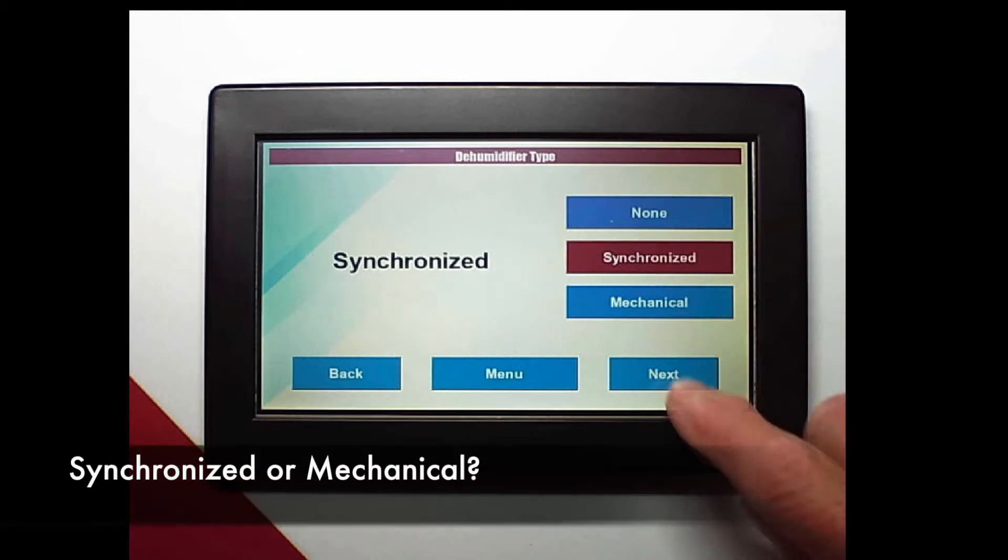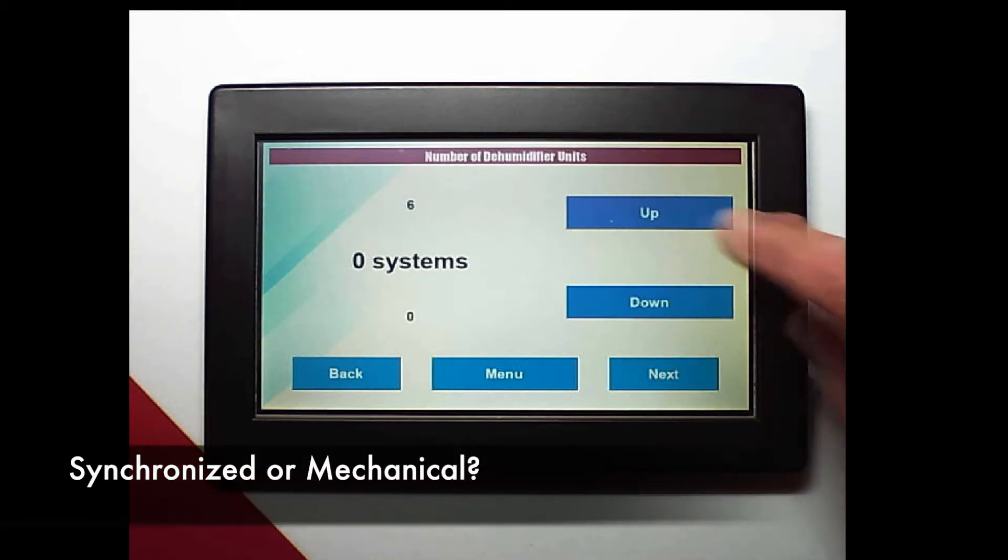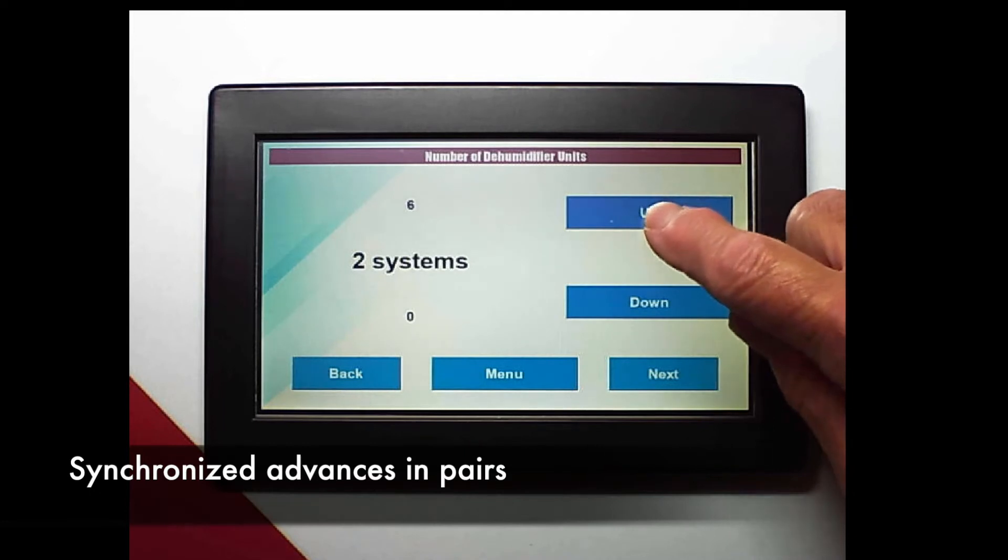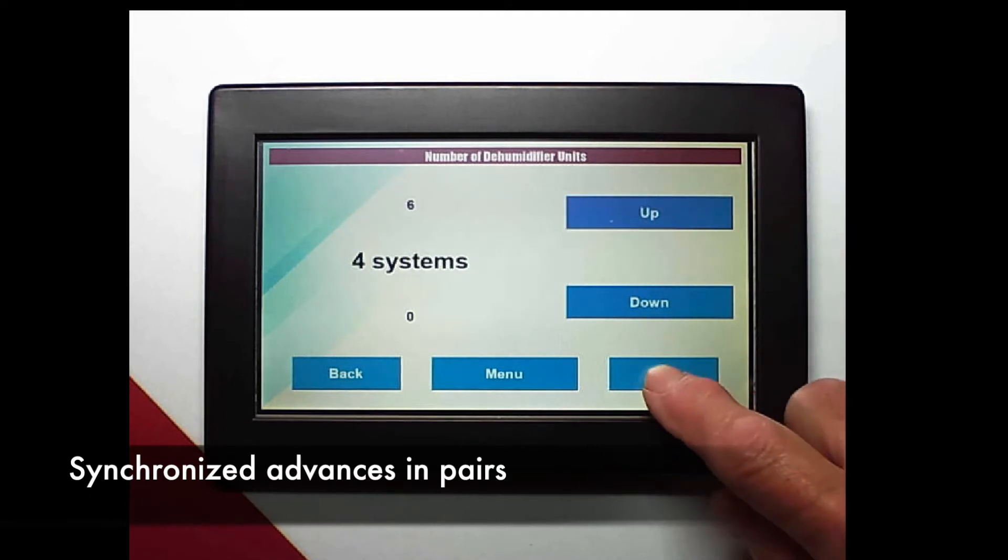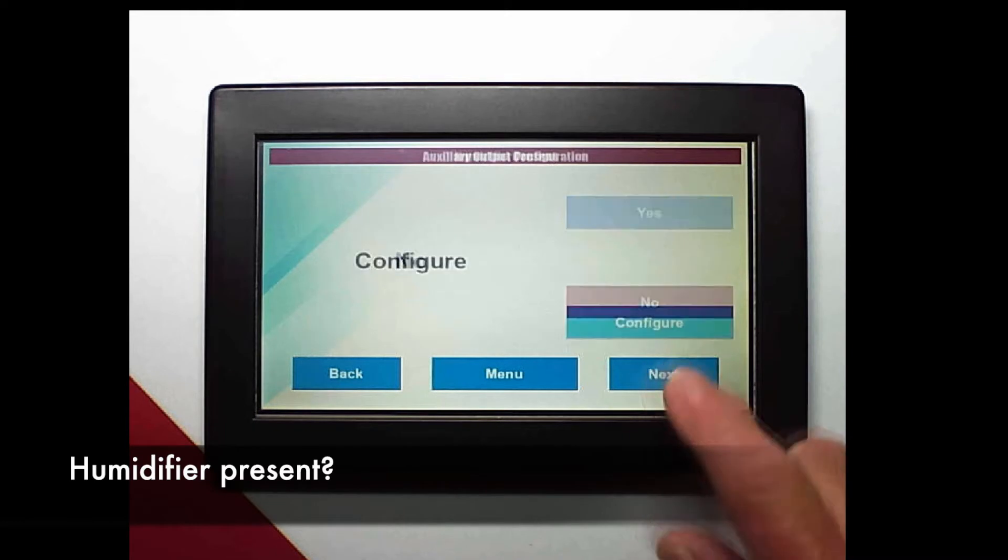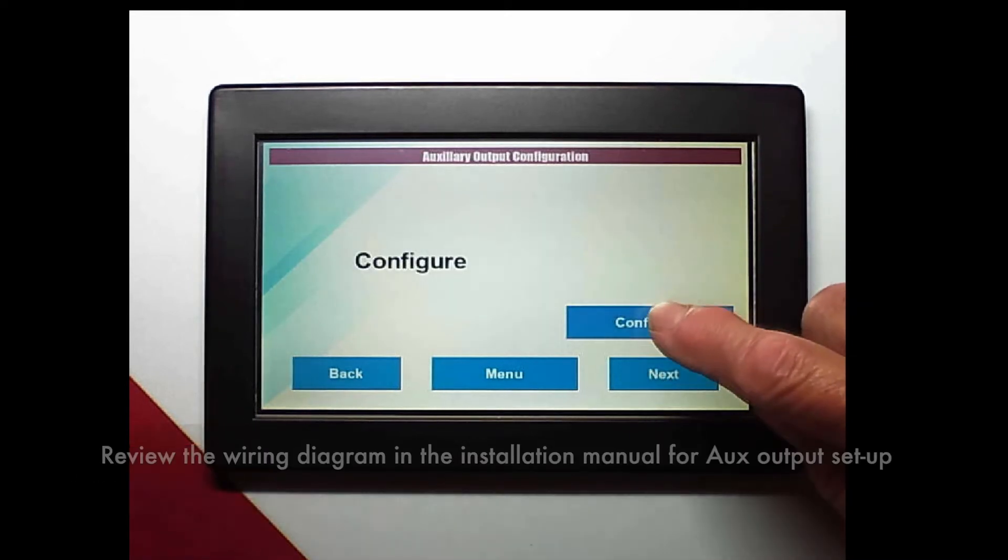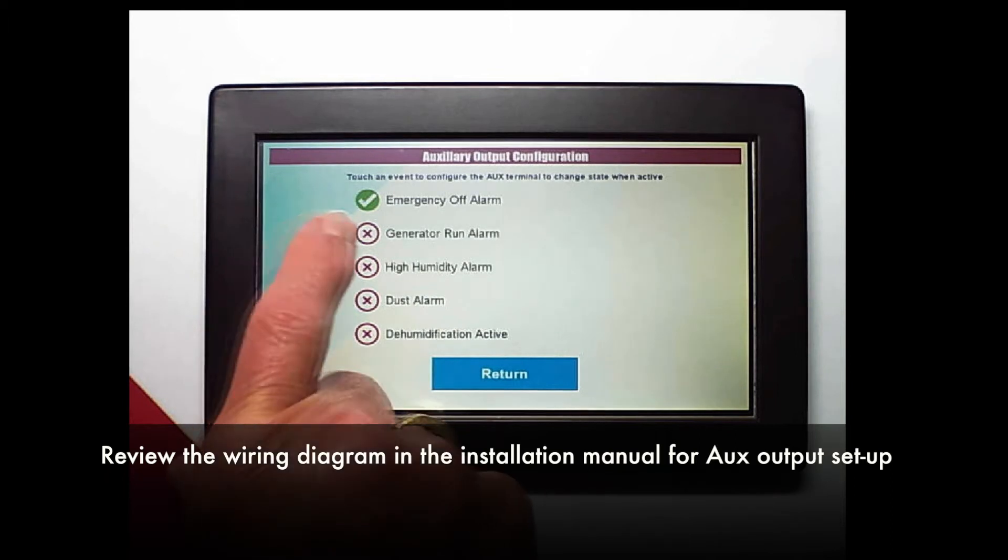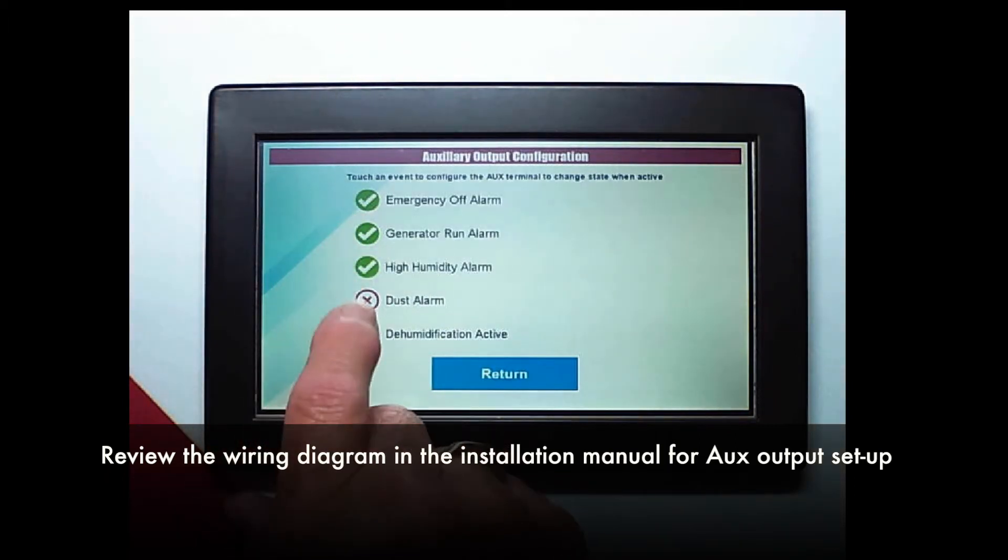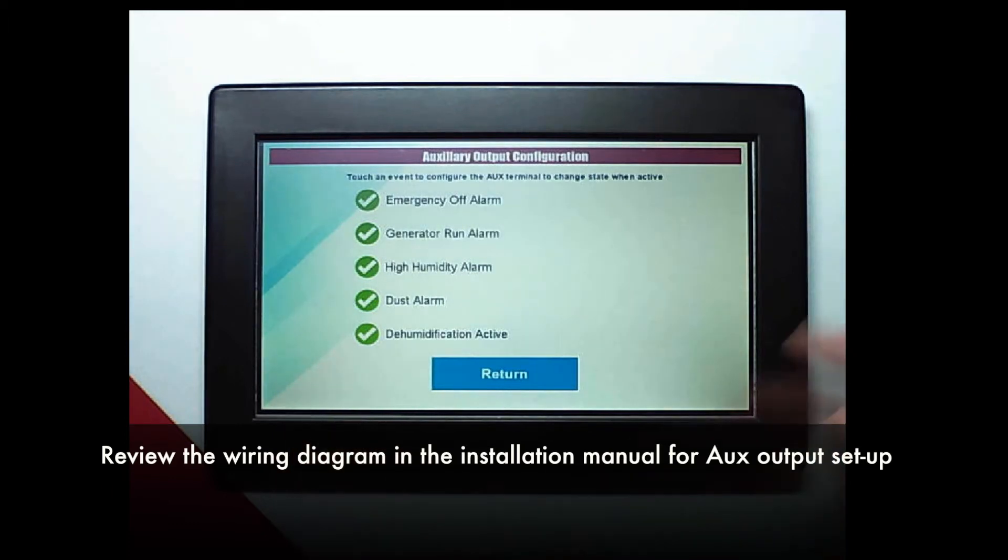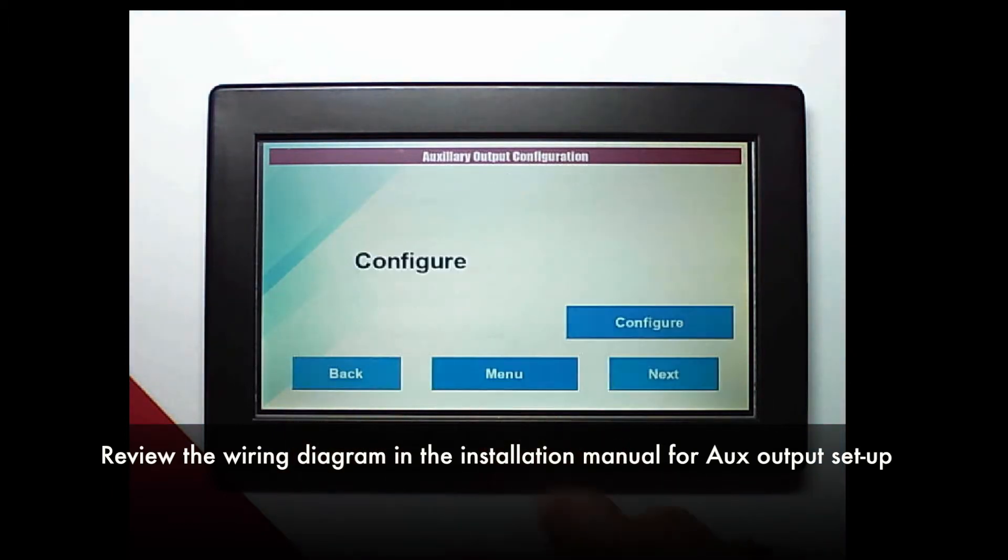We could choose mechanical or synchronized. If we choose synchronized it will advance in pairs. A humidifier present? No. We need to configure the auxiliary output. There are options here that we can select and if we wire the unit and set it up properly our damper will spring closed during all of these events.